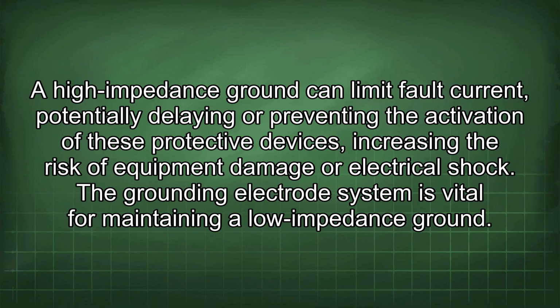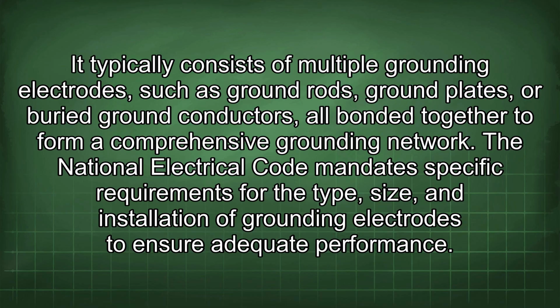A high impedance ground can limit fault current, potentially delaying or preventing the activation of these protective devices, increasing the risk of equipment damage or electrical shock. The grounding electrode system is vital for maintaining a low impedance ground. It typically consists of multiple grounding electrodes, such as ground rods, ground plates, or buried ground conductors, all bonded together to form a comprehensive grounding network.